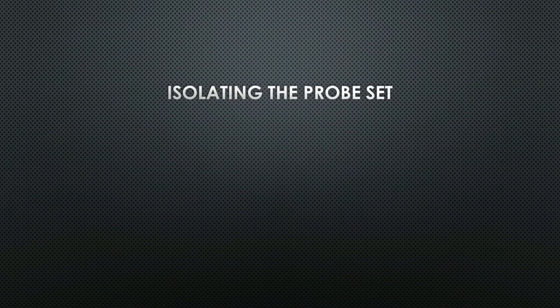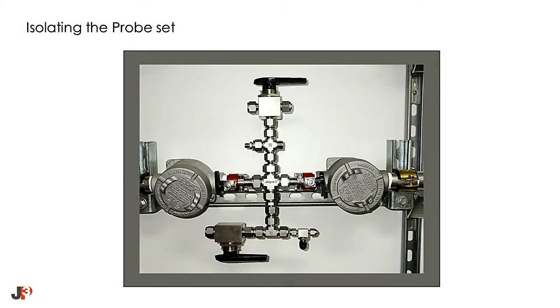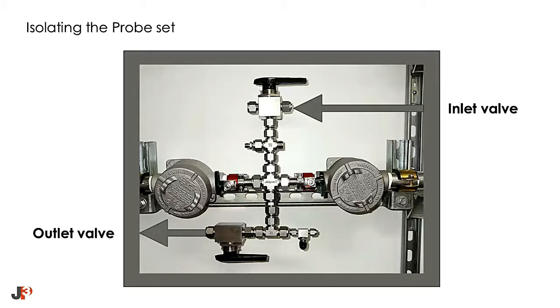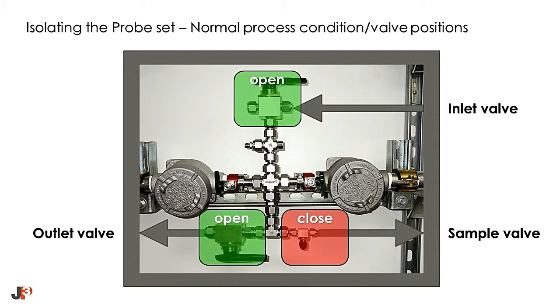Isolating the probe set. Let's take a closer look at your probe set. The top valve is the inlet valve. The larger bottom valve is the outlet valve. The smaller bottom valve is the sample valve. During normal process conditions, the inlet valve and the outlet valve are both open and the sample valve is closed. This yellow line represents process flow during normal process conditions.